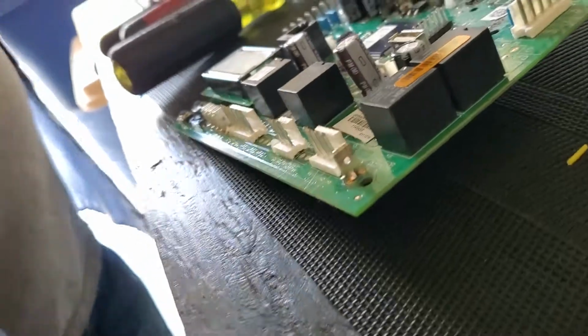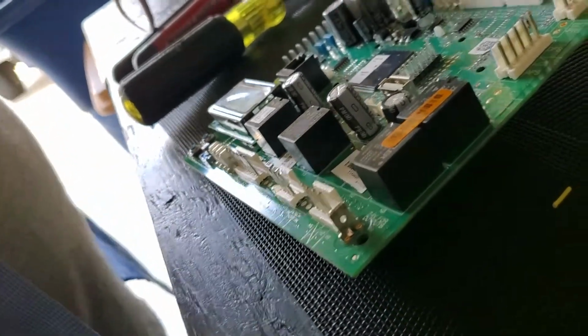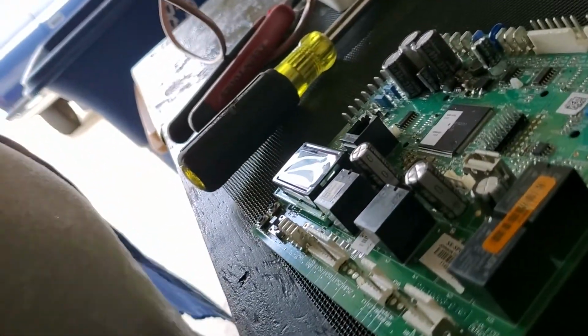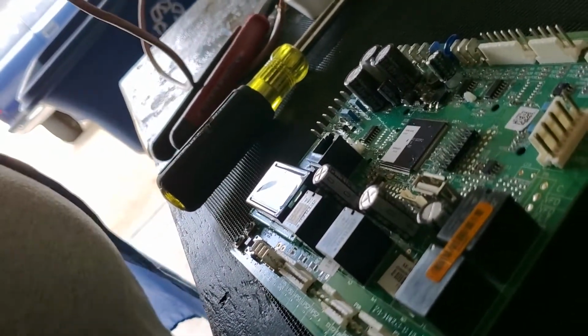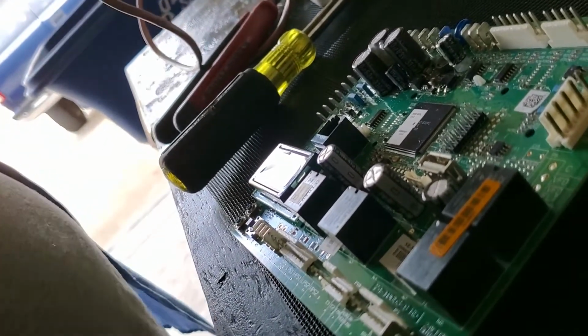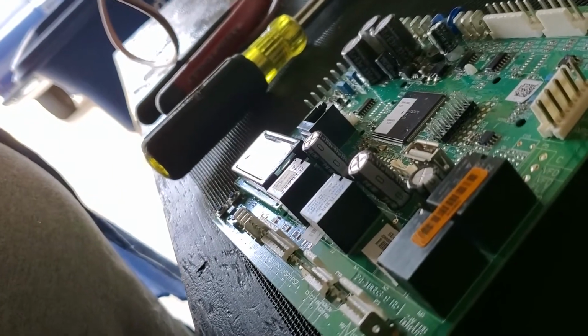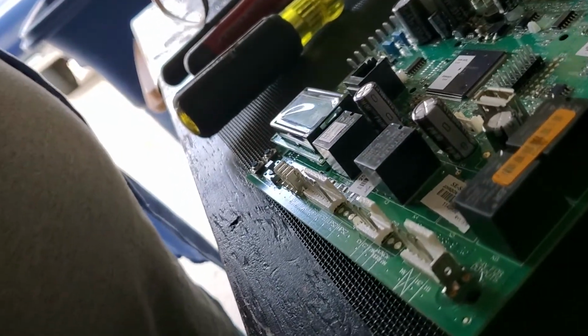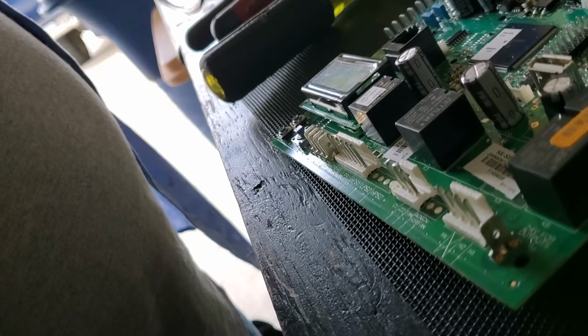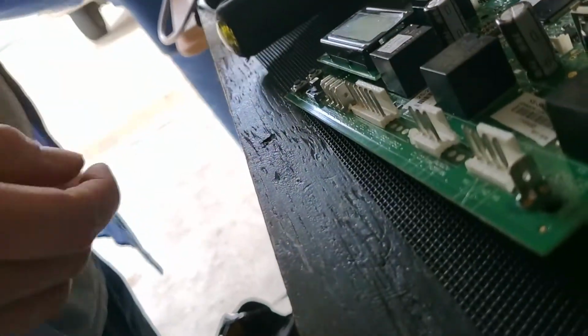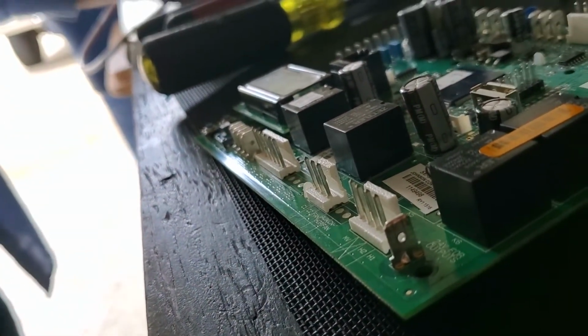So if this was a heat pump right now, let's say I pulled the old thermostat wire off and they had an orange wire landed on OB originally. I would take that same orange wire and land it on OB right here. Then I take my white wire, which is auxiliary heat. Actually, if we were doing that, you'd put it on the E, for emergency heat. So if it's a heat pump, it's something you have to recognize when you pull the old thermostat off.